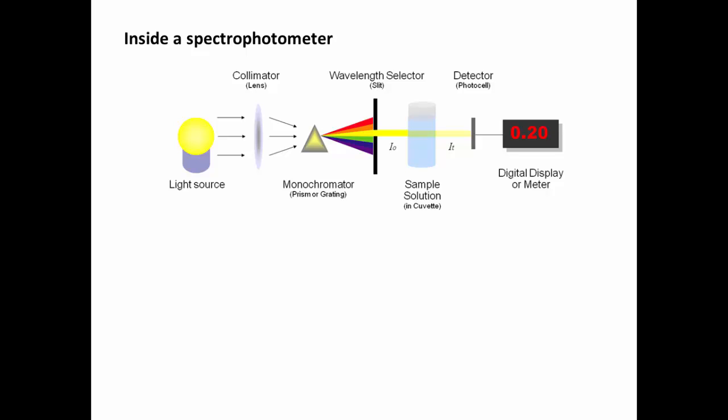If we look inside a spectrophotometer, these are the basic parts. There's a light source, a lens, and then there's a prism to separate the white light into different wavelengths. The light then passes through a wavelength selector, which is basically a tiny little opening. And it's made small enough so that only one color or wavelength of light is able to pass through.